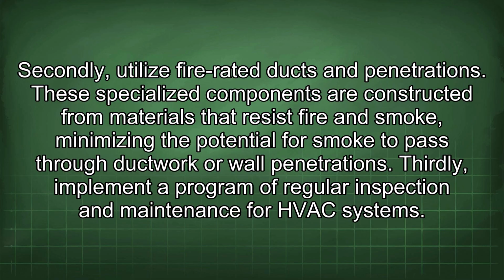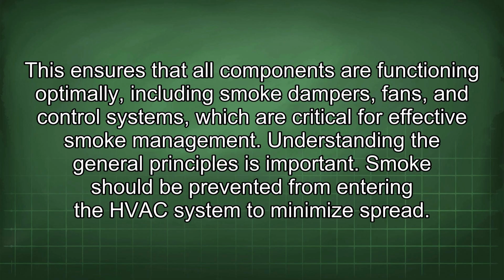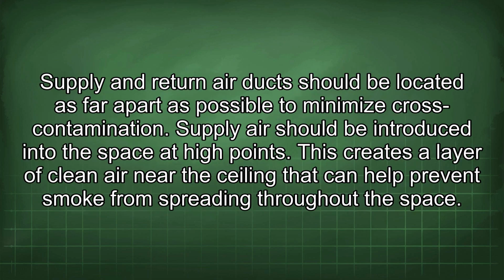ductwork or wall penetrations. Thirdly, implement a program of regular inspection and maintenance for HVAC systems. This ensures that all components are functioning optimally, including smoke dampers, fans, and control systems, which are critical for effective smoke management. Understanding the general principles is important. Smoke should be prevented from entering the HVAC system to minimize spread. Supply and return air ducts should be located as far apart as possible to minimize cross-contamination.